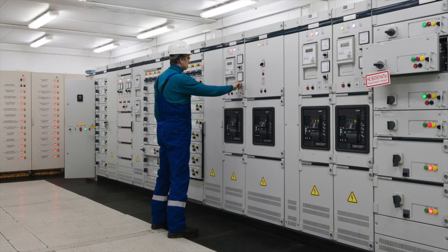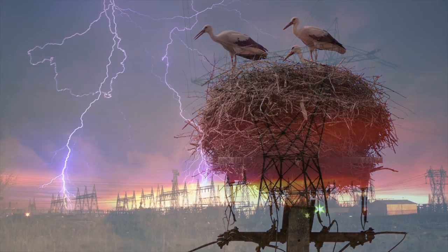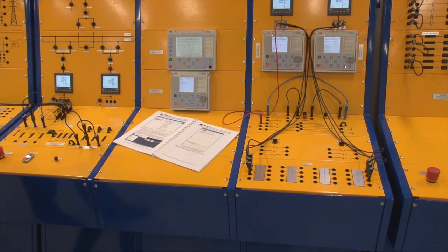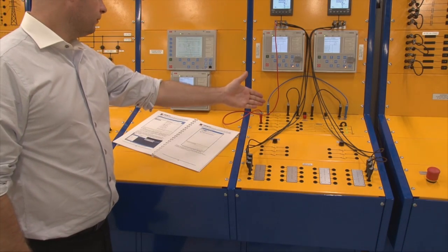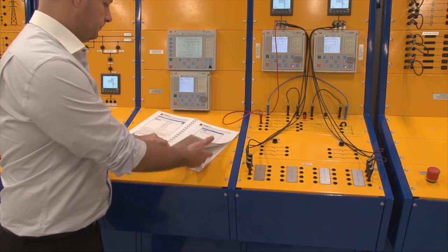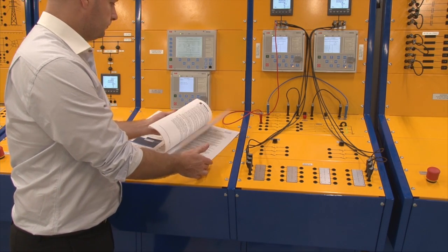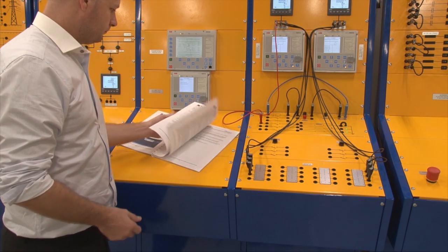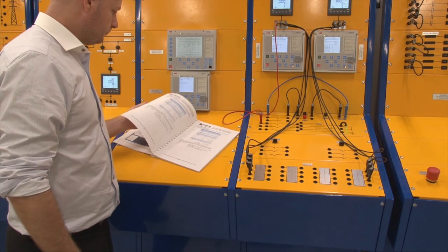As in reality, the substation is guarded from internal and external faults by the latest IED relays, which provide protection for the step-down transformer, the incoming high voltage lines, and the outgoing medium voltage feeders. The 2230 also houses a fault simulator for easy connection and control of fault situations.